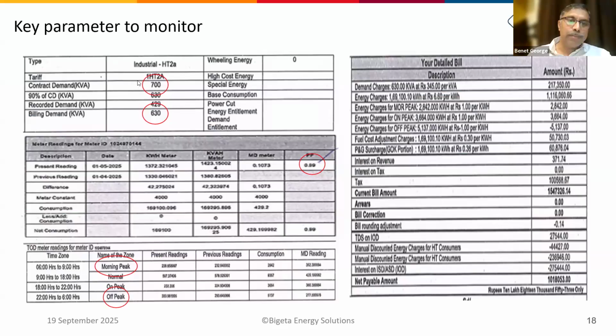90% of the contract demand is 630, but the recorded demand is only 429. Even though their demand is much lower than the contract demand, they have to pay minimum 630 kVA demand charges. Typically it can be something between, so in this case, it was 345 rupees per kVA. Now you can calculate whether they can do a demand reduction, or whether we need this much demand, and whether any future expansion plan is there or not. If there is no plan for expansion, you can also think whether we can reduce that demand.